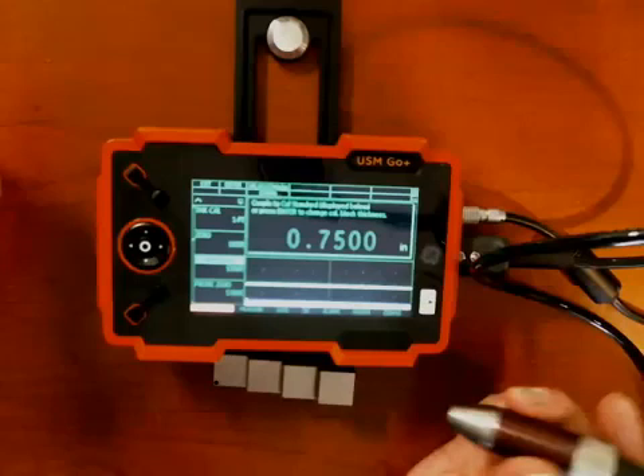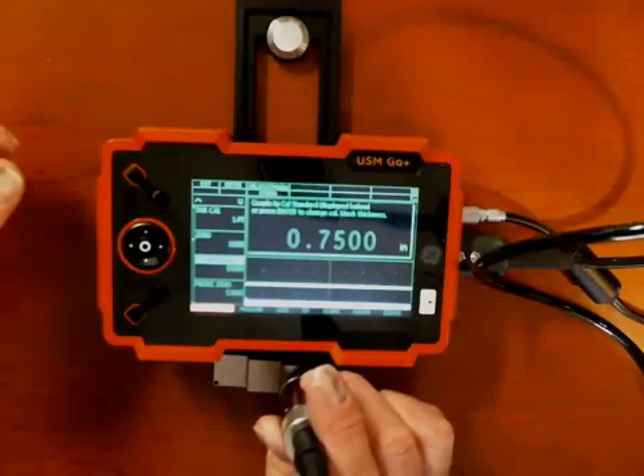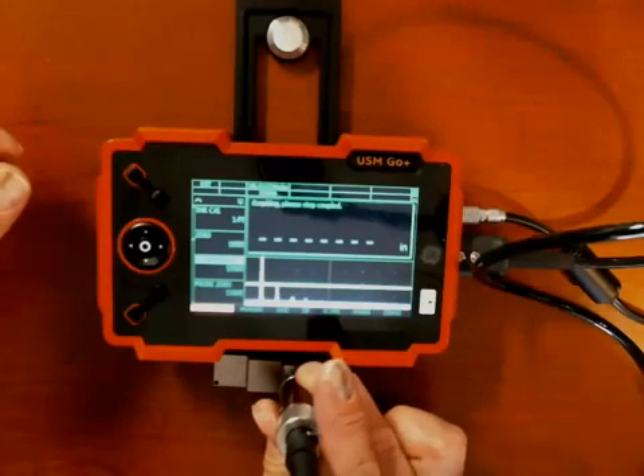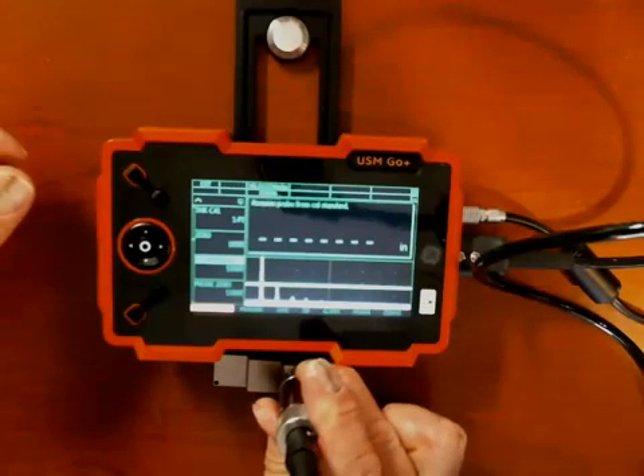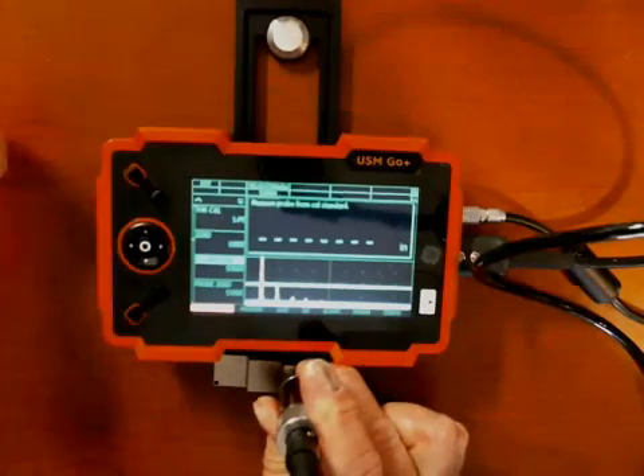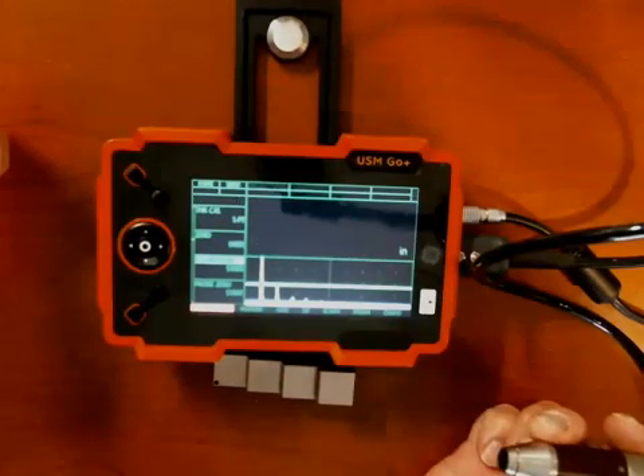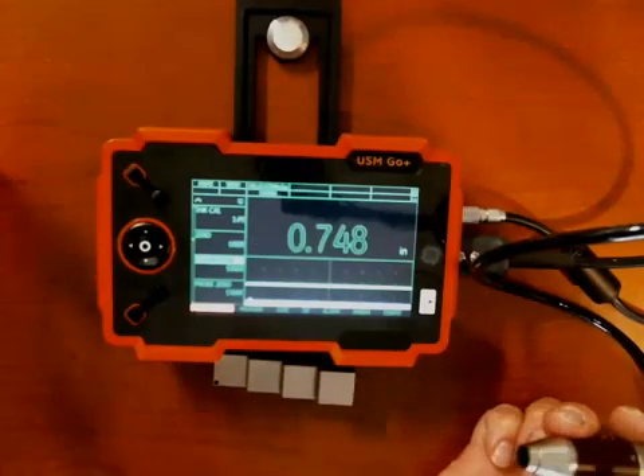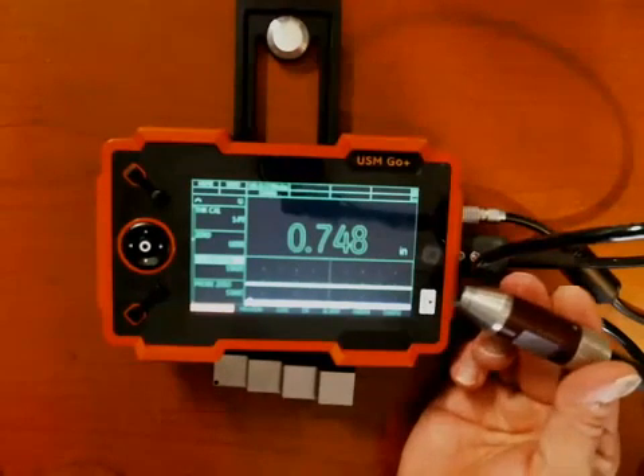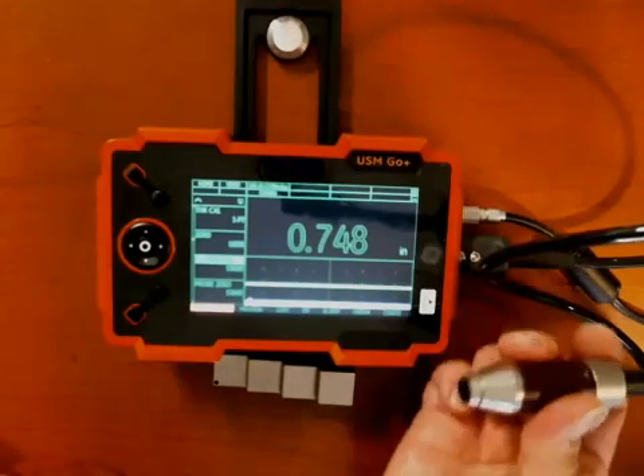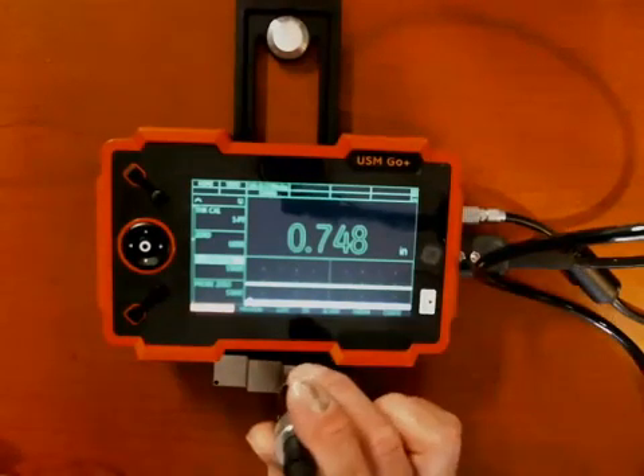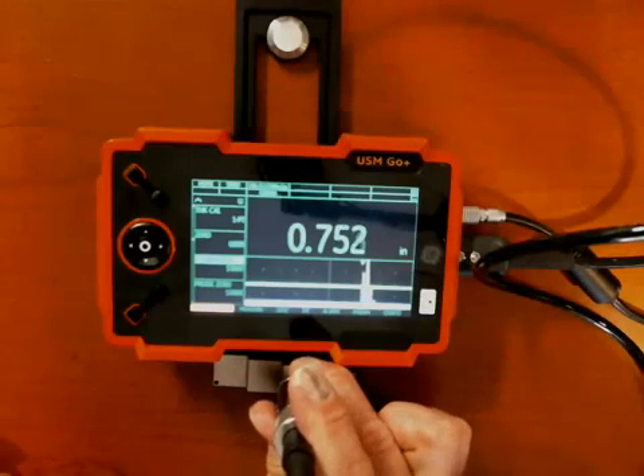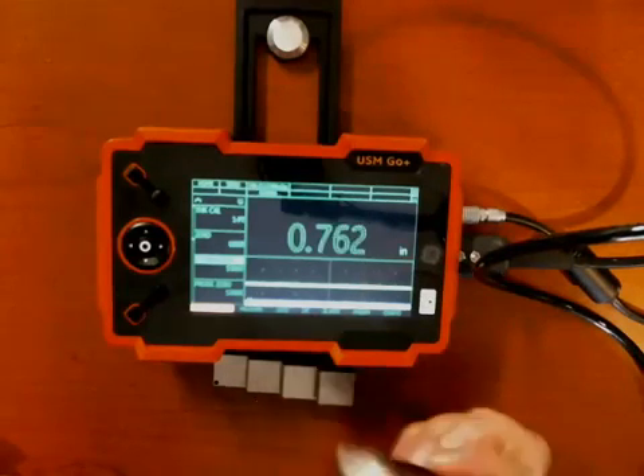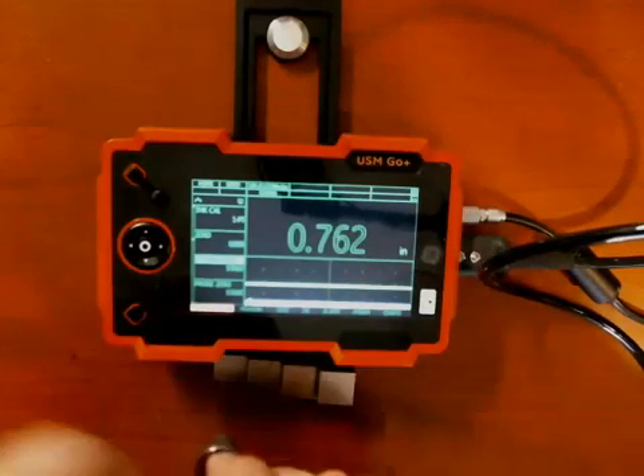It says, okay, you wanted 3/4 inch, so put the probe on the 3/4 inch block. Acquiring, please stay coupled. Now it says remove the probe from the cal standard. Okay, and it's all ready to go. It has completed the calibration process. So now if I take my probe back to the 3/4 inch block, 751, it's just a little bit high.